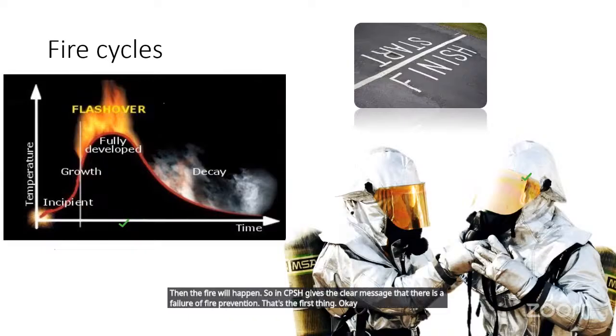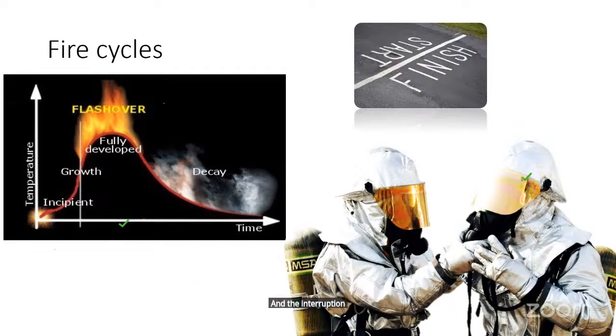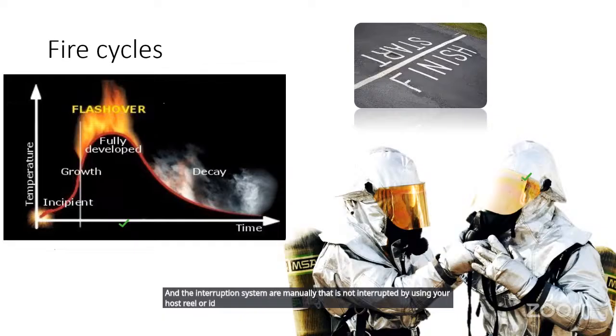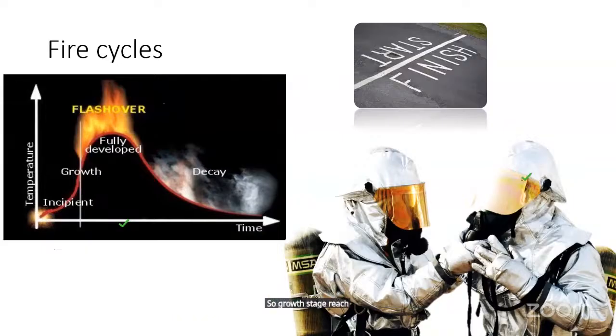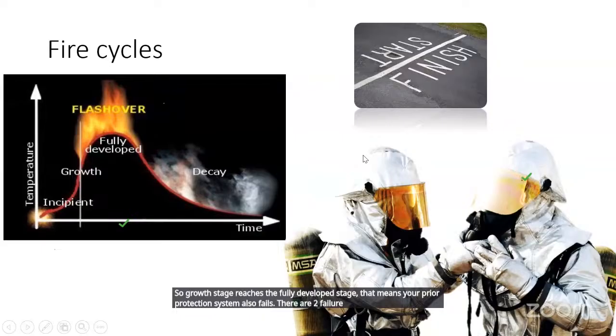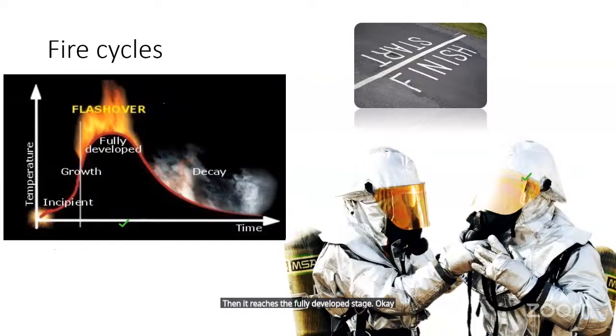The second stage: fire has happened at your industry or any place. Suppose that fire is not interrupted by the automatic fire detection and interruption system, or manually by using your hose reel or hydrant system, or the automatic sprinklers cannot extinguish the fire. Then that fire will grow to its fully developed stage. That means your fire protection system also fails. There are two failure stages. One is that the fire prevention stage failed, and the other is that the fire growth and fire protection system also failed. Then it reaches the fully developed stage. In the previous video we have seen that within 4 minutes the fire will spread like anything.